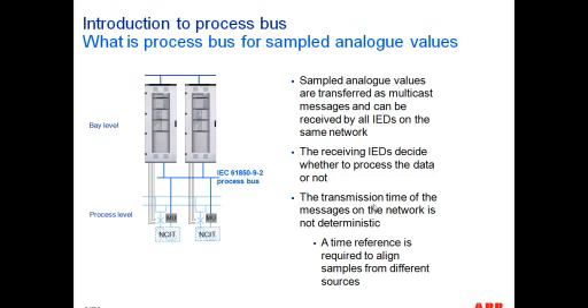The transmission time of the messages on the network is not deterministic, which means that a time reference is required to align samples from different sources. Again, going back to a case where you may have a breaker-and-a-half scheme or a ring bus scheme where there are going to be two merging units, there needs to be a source of time synchronization for those two merging units and your relay, so that those samples can be individually aligned at the IED level and the IED can perform its protection functions accurately.